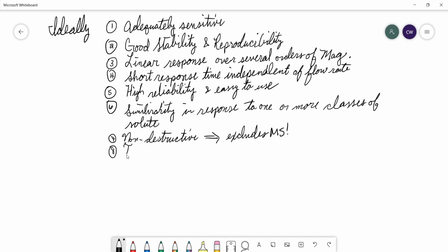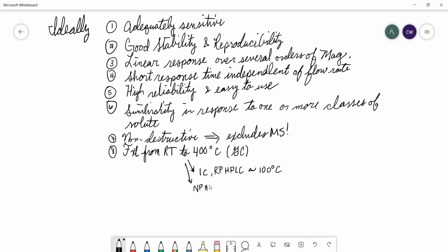And we want these things to be functional from room temp to 400 degrees C. Now, 400 degrees C is the cutoff for GC. For ion chromatography and reverse phase HPLC, the temperature would never exceed 100 C, so we want it to be functional at least to around 100 C, because if we go above 100 C, we'll explode the system. And in normal phase HPLC, that temperature could be even lower, because we don't want to go over the boiling point of the mobile phase.